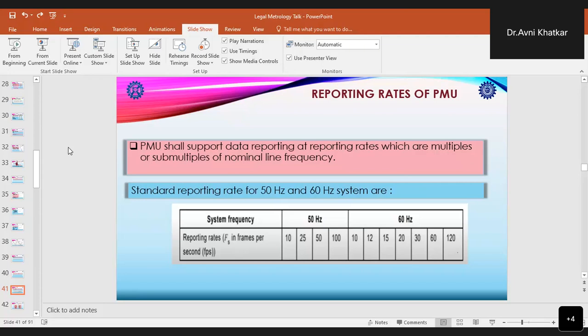So for 50 hertz, the reporting rates are 10, 25, 50 or 100, which, as you can see, are multiples or sub-multiples of the nominal line frequency, which is 50 hertz. Similarly, for 60 hertz, the multiples or sub-multiples can be 10, 12, 15, 20, 30, 60 or 120. They are the standard reporting rates chosen for the 60 hertz system.